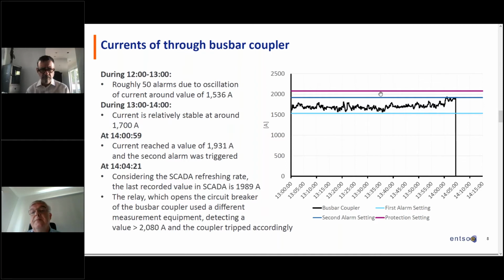And so we see here the protection setting, which is the top line, and the second alarm setting, which is the second line. And here we see that the busbar coupler disconnected a little bit before the measurement was still at the second alarm, while apparently in reality the flow was already at the protection setting. So yeah, a little measurement error here. The protection equipment is of course looking at the 50 Hz signal, while the measurement in the dispatching is refreshed every 2 to 4 seconds, and it's not, of course, exactly the same value at all times.